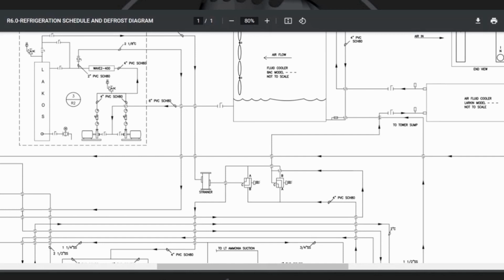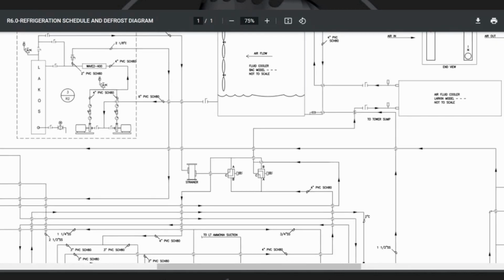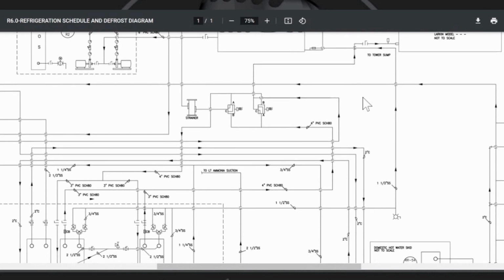Those two valves are there so that once a week we reverse the flow through the plate heat exchangers. When you read up on the maintenance for plate heat exchangers, if you ever have to run acid through them, they want you to run it through backwards, and they want you to run twice the GPM. Well, we can't run twice the GPM, but we can reverse the flow. So if we ever had to put acid in the system, we can just use these valves, put the acid in the tower, reverse the flow, run it for a day, drain and flush the tower, put the neutralizer in, and we're back in business.